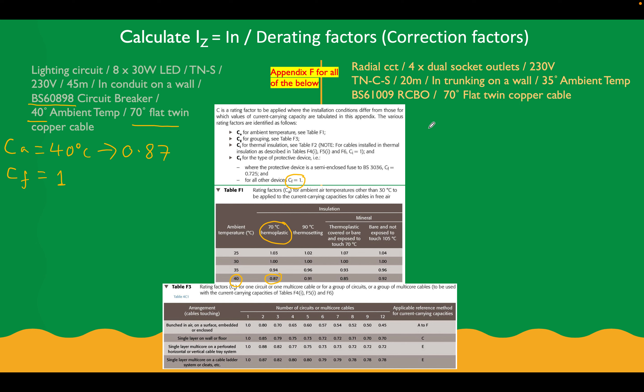Now let's move on to the radial circuit side and extract our correction factors. Our CA this time is 35 degrees — slightly different, a bit cooler. Same type of cable: 70 degree flat twin and earth. Looking at the table for 70 degree cable at 35 degrees, our correction factor CA is going to be 0.94.